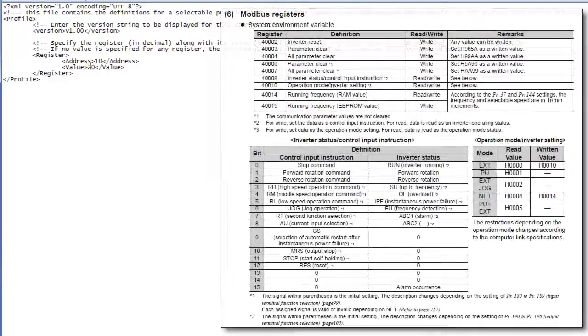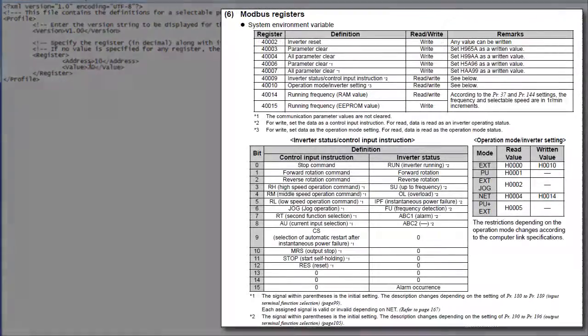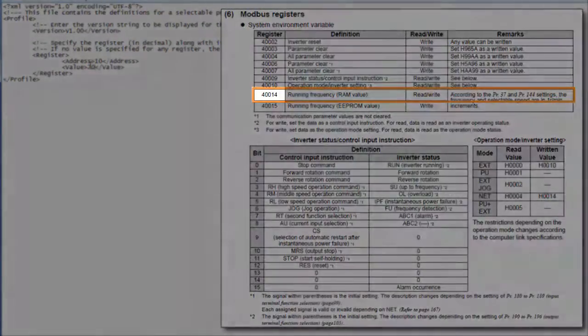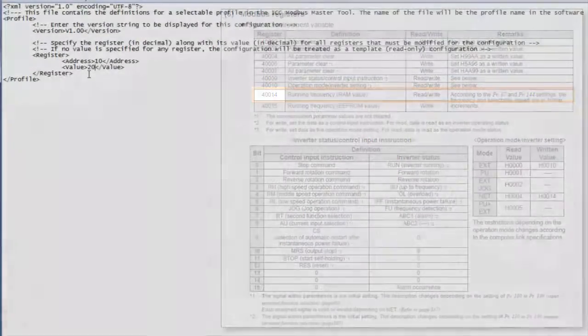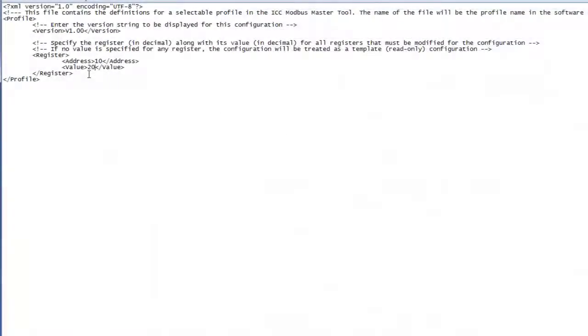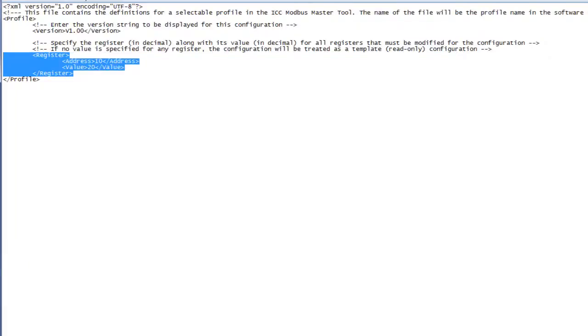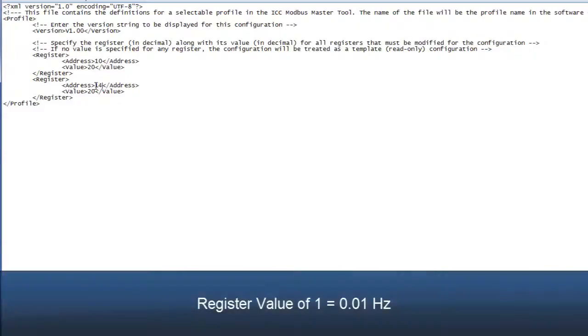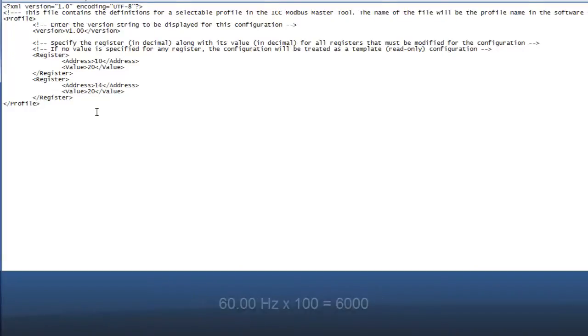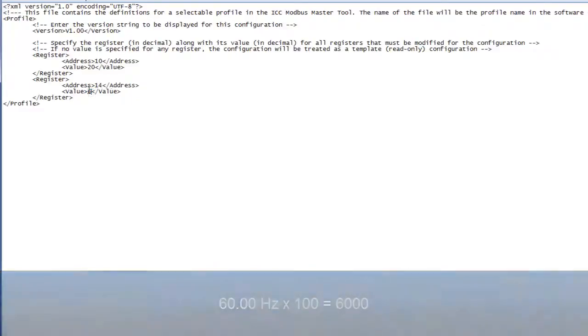The next parameter is the running frequency. The register for it is 40,014, or holding register 14. We'll just copy and paste our last register definition. And we'll enter 14 for this register's address. Because this register is scaled to allow setting the frequency down to a hundredth of a hertz, we need to multiply our frequency by 100. So, to run the drive at 60 hertz, we need to set this register to 6,000.